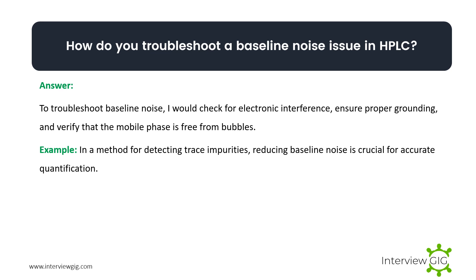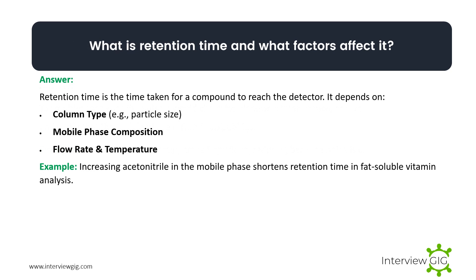How do you troubleshoot a baseline noise issue in HPLC? To troubleshoot baseline noise, I would check for electronic interference, ensure proper grounding, and verify that the mobile phase is free from bubbles. Example: in a method for detecting trace impurities, reducing baseline noise is crucial for accurate quantification.